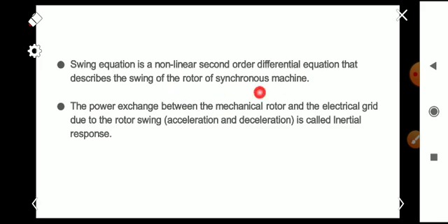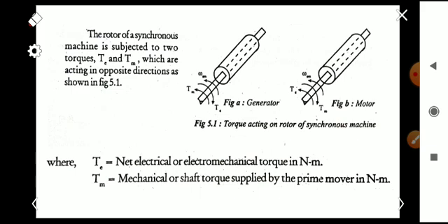The swing equation is a nonlinear second-order differential equation that describes the swing of the rotor of a synchronous machine — that is, the change in speed (acceleration or deceleration). The power exchange between the mechanical rotor and the electrical grid due to this rotor swing is called Inertial response. As shown in the figure, we are considering the rotor of a synchronous machine — whether it is a generator or a motor.